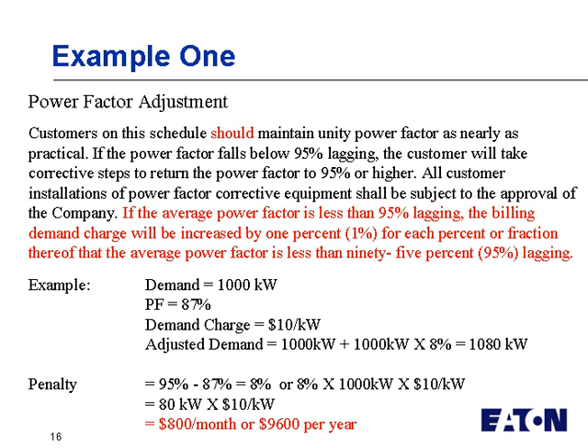So that really means that your penalty is 80 kW times the demand charge, or $10, or $800 a month, or $9,600 a year. And $9,600 a year is quite a bit of money to be able to spend on power factor correcting equipment, and you may be able to pay that off in 6 months, for example.